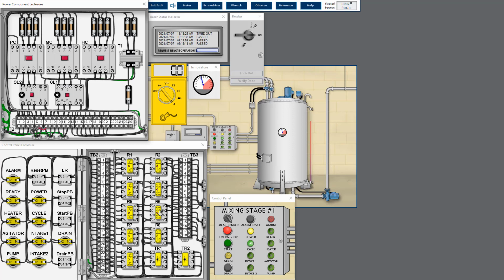As for inrush current or rotor lock current, this is the highest current, maybe more than 10 times the full load current during motor starting. Another one is the earth fault current. Earth fault current is also very high. But usually we are unable to measure it because by the time a fault happens, the breaker will trip or the fuse will blow immediately.